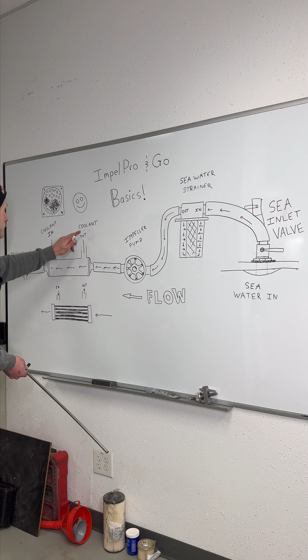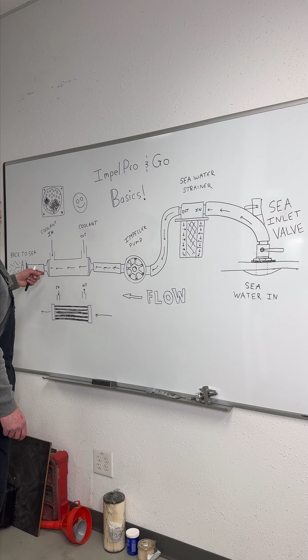Especially on generators, when they're running they're normally at a rated speed. So this whole system is designed knowing that your coolant in and coolant out will take so much cold water to keep that, let's say, at 180 degrees. So if we start to clog it up, we're no longer happy - our engine's probably hot, or we have an alarm.